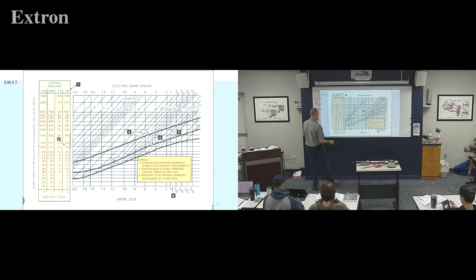So I'm just gonna backtrack and we'll come up with one. Okay. So if we've got a 14 volt system and we want to run it 8 foot at, that's a lot of amps, 30 amps. So 14 volt, come down to 8 foot, come over to, oh, see now I didn't do my 30 amps to make sure I don't lose my line. 30 amps. If I drop straight down, I'm basically at a 12 gauge wire that it would say to use. But what we didn't spell out ahead of time is we would have said, hey, is this continuous use or is it intermittent? And if I said, well, it's actually continuous and it's in a bundle. Well, right here, I'm down below this continuous bundle loop.